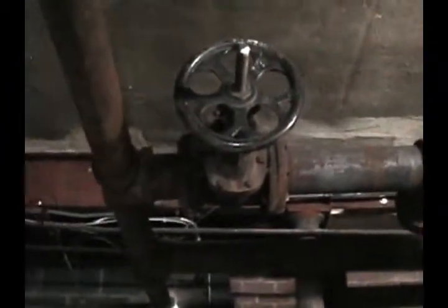What's your take on the boilers, Gary? Are they at the end of their useful life? Complete junk. They're almost 30 years old. One of them is definitely no good, the auxiliary, they say. It could last a few more years, but the number one boiler's gonna go. They both run at the same time. 84.75% efficiency in 1984. You can't get parts. The plates are cracking. The insulation's gone on the rack.